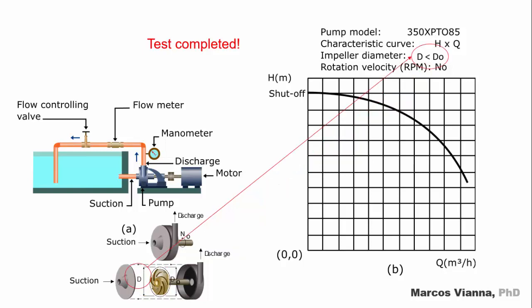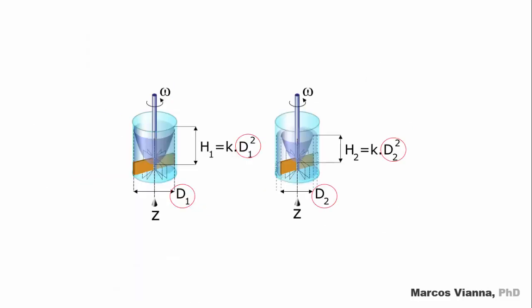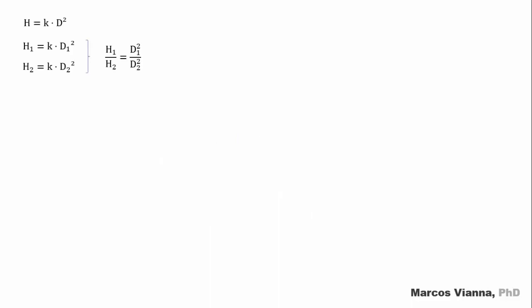But what will happen if we run the same test for a smaller impeller? Another curve will be obtained. Here it is, in the technical material supplied by the manufacturer. We can obtain this new curve using the concepts that we have seen before. Let's remember. The height difference of water between the edge and the center is proportional to the square of the diameter. So, this relationship can be obtained.